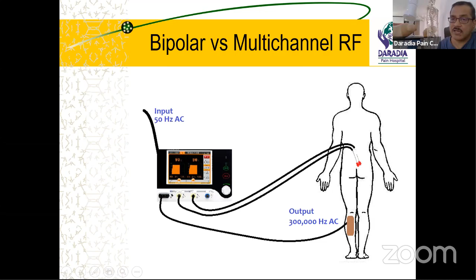So the machine divides like 2 machines or 3 machines or 4 machines. The ground plate is common, but there is an individual circuit between each of the active electrodes. So that is your multi-channel, having multiple lesions together. This is the difference between the bipolar and the multi-channel radio frequency.